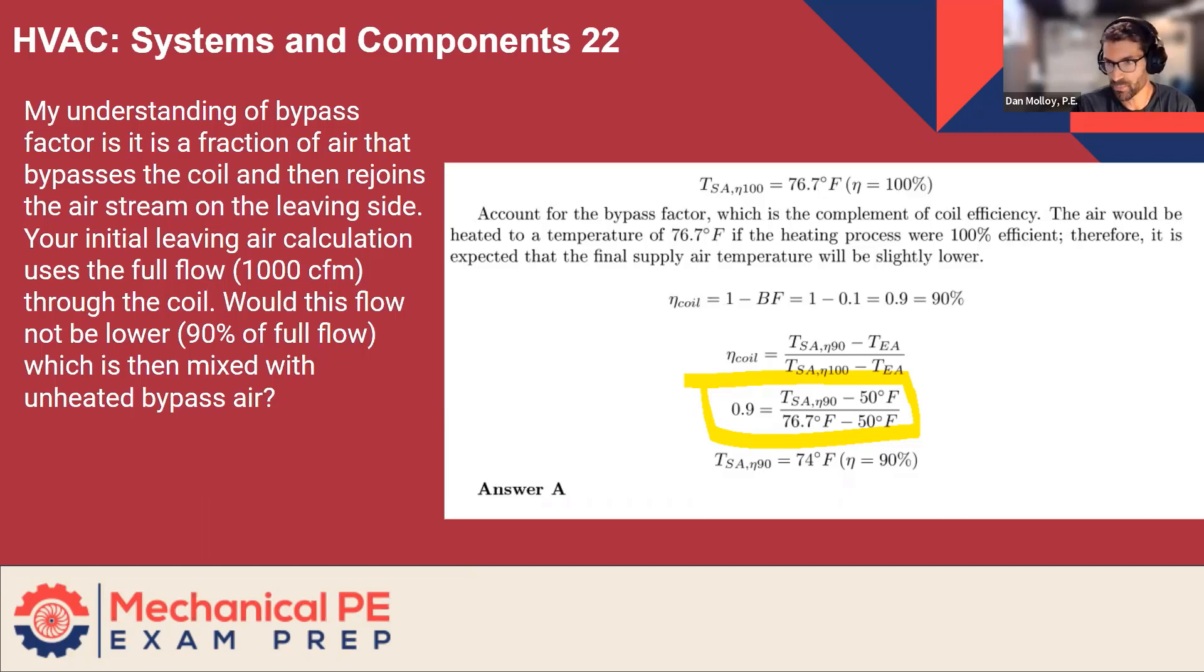For context, this problem was about a steam coil with a bypass factor of 0.1, which is to say it has a coil efficiency of 90%, because the coil efficiency and the bypass factors are complements of one another.